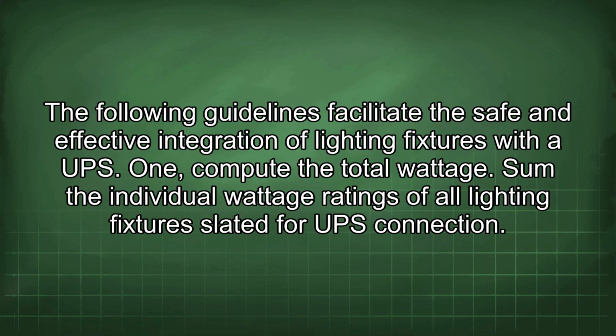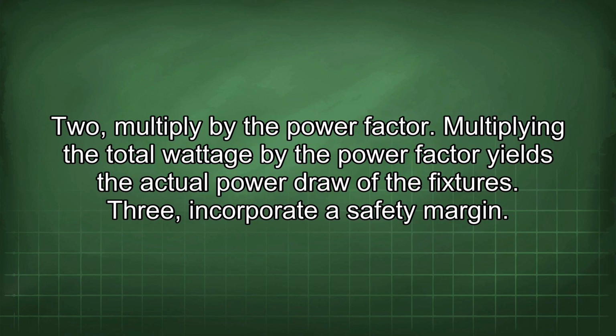The following guidelines facilitate the safe and effective integration of lighting fixtures with the UPS. 1. Compute the total wattage. Sum the individual wattage ratings of all lighting fixtures slated for UPS connection. 2. Multiply by the power factor. Multiplying the total wattage by the power factor yields the actual power draw of the fixtures.